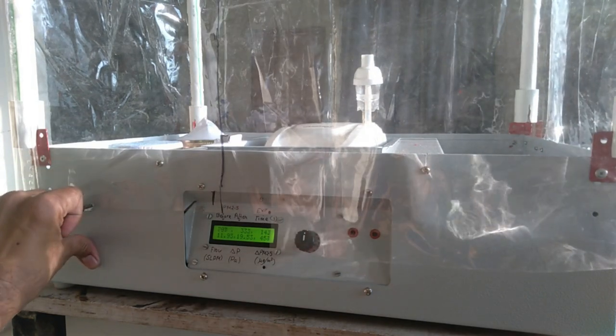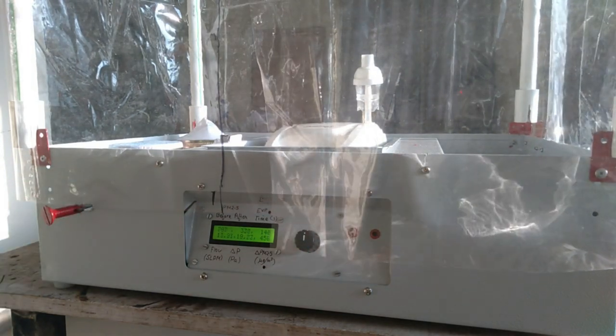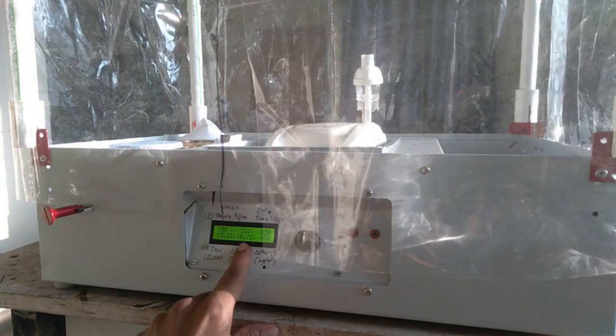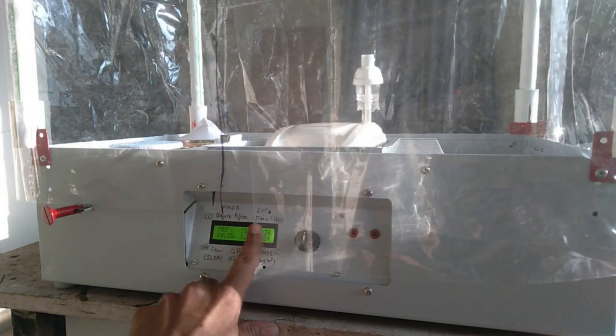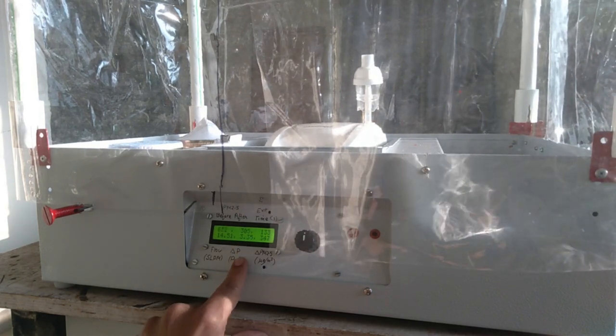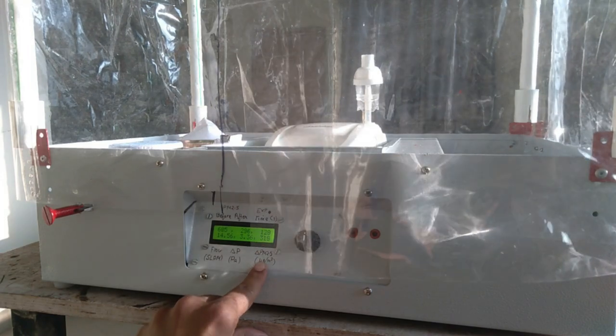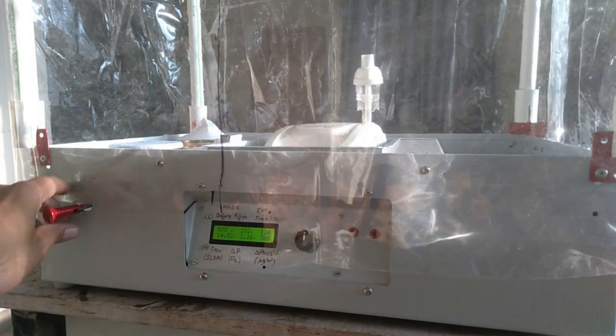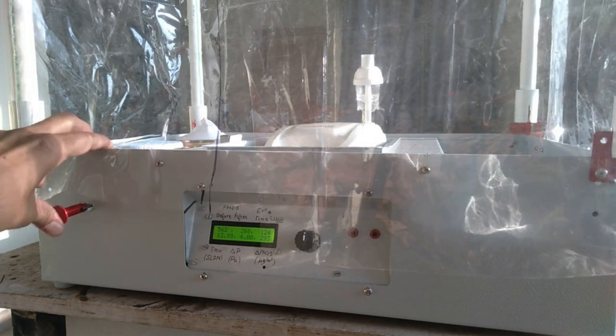When we select the masks, for example, right now it has been selected to the surgical mask, we see that the pressure drop across the mask is quite low. It's around 3 to 4 pascals. And the airflow is also high. It's around 15 to 16 liters per minute.